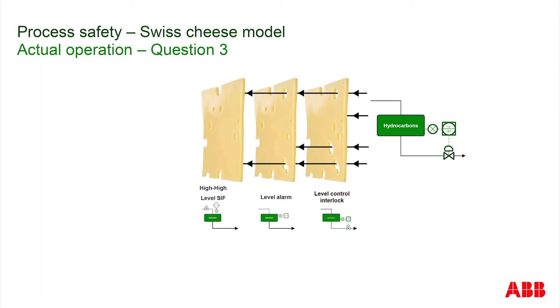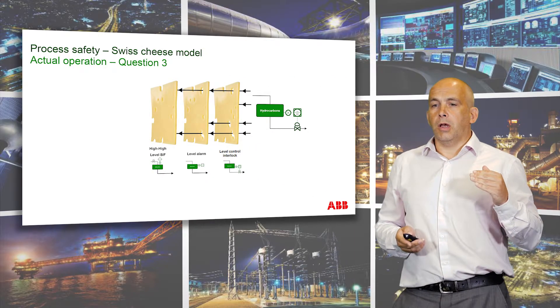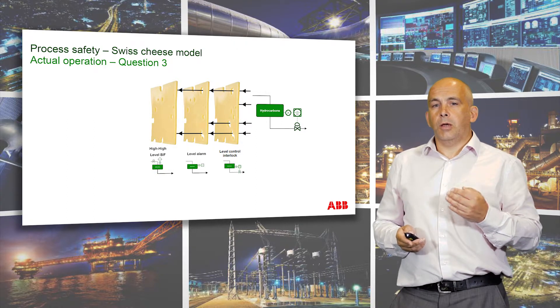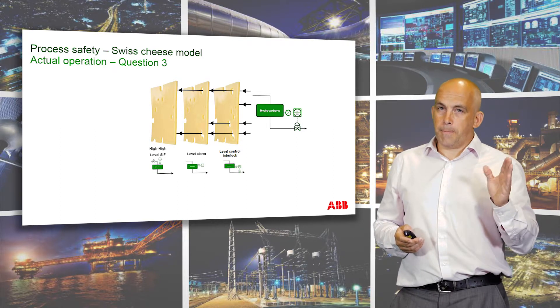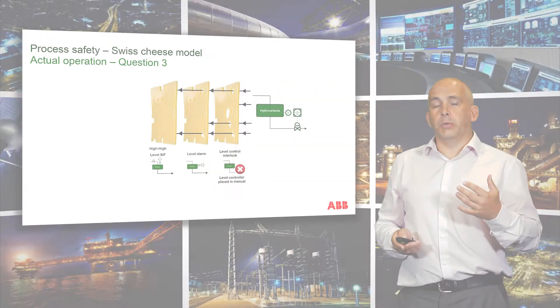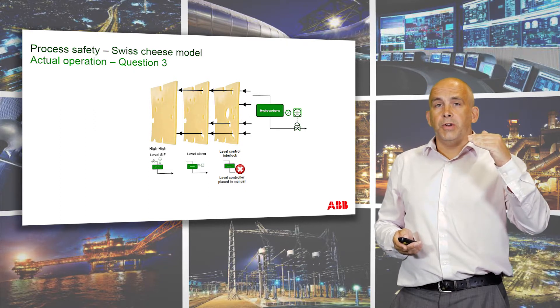So what happens in operations? Consider that vessel — the level isn't controlling very well at the set point, maybe due to a disturbance. The operator thinks he can control it better than the controller and places it into manual. As soon as that occurs, we're actually defeating that particular barrier — in our Swiss cheese analogy, we're introducing a new hole. Because the controller is now in manual, the level isn't controlling well at all, and the level starts rising, hitting the alarm threshold.